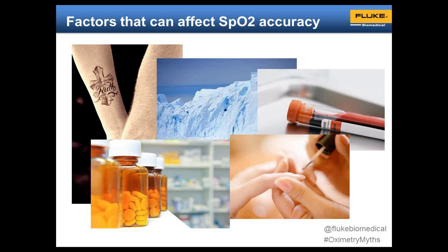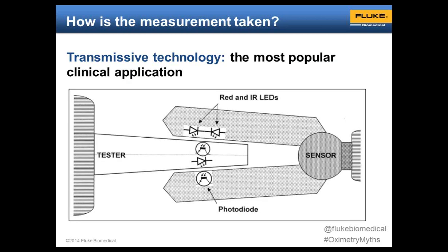This is an example of a transmissive technology, the clip-on, a finger if you will. So both a tester or a finger can be placed into this sensor. And usually there's a red and IR LED transmitter on one side and a photodiode detector on the other side. So light in different wavelengths is shined through the finger and detected on the far side, and that measurement is compared to the R-curve to then come up with a % oxygen saturation. So the tester blocks the emitter and emits its own light source into the photodiode is how a tester works.